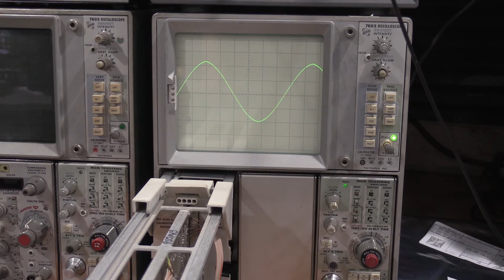Okay, well, we're back, and I had to tear the whole thing down one more time. Turns out on the 10 millivolt range, I did not have enough spring tension on the back side of the switch, because on 10 millivolts it's straight through. It doesn't go through any of the attenuators. I did not have enough spring tension on the clips, so a little bit of wiggle, just bumping the control, was enough to cause it to come and go. But I've got it now, so I've got the attenuator all fixed.